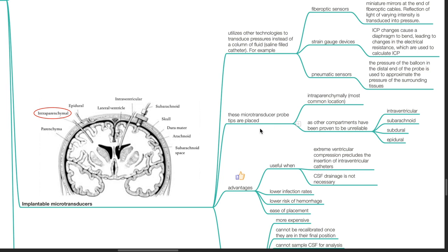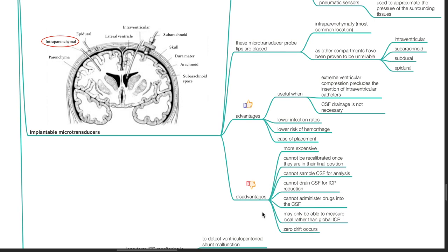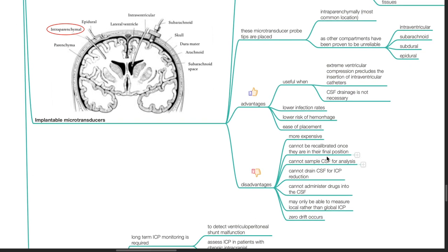These microtransducer probe tips are placed intraparenchymally, which is the most common location. Other compartments such as intraventricular, subarachnoid, subdural, and epidural locations have been proven to be unreliable. Advantages of implantable microtransducers: it is useful when extreme ventricular compression precludes the insertion of intraventricular catheters and where CSF drainage is not necessary. There are lower infection rates, lower risk of hemorrhage, and it is easier to place compared to EVD. Disadvantages: It is more expensive, it cannot be recalibrated once in final position, it cannot sample CSF for analysis, cannot drain CSF for ICP reduction, cannot administer drugs into the CSF, it may only measure local rather than global ICP, and zero drift occurs with implantable microtransducers.